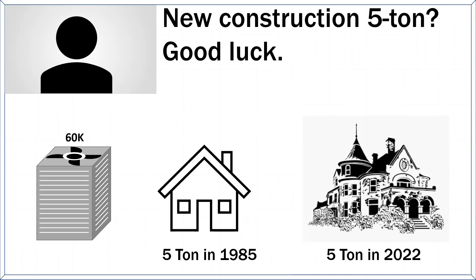Everything is more restrictive. When he says 5-ton systems don't work, it doesn't mean they all fail and need to be replaced. He means you're never getting the capacity out of them that you think you are. So with a house like this, we're better off splitting it into smaller systems. Unfortunately, that can put us into those little black hole areas.